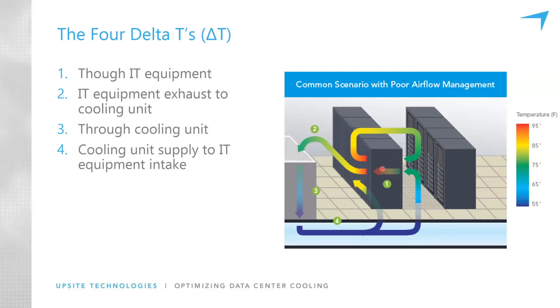Delta T4 — why does air heat up so much from the time it leaves the cooling units before reaching the IT equipment intakes? The cause is exhaust air recirculation: hot exhaust air finds its way into the cold aisle flow path approaching the IT equipment, mixing with and warming up the conditioned air. The way to reduce delta T4 is through airflow management improvements: sealing all cable openings, sealing all cabinet spaces, and ensuring aisle containment doors on the ends of rows, something over the top of the cabinets, or containing the hot air so it can't get back into the cold aisle. Eliminating exhaust recirculation is the only way to reduce delta T4.